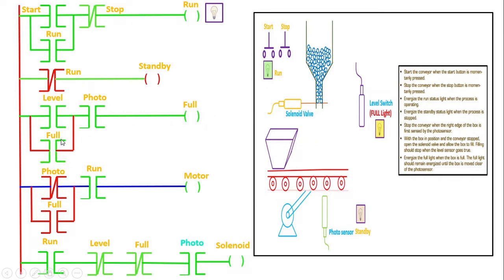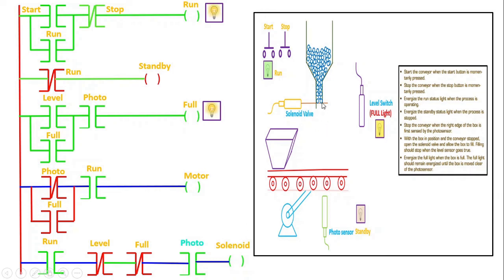Once the level switch goes high, the run contact gets energized and the full status coil becomes energized. Due to latching, the full contact address is also energized here, so the full light is now glowing. The level was energized and the full sensor was energized — as a result the normally closed level and full contacts become open circuit, the supply is cut off, and the solenoid valve which was open becomes closed again, so the substances stop flowing.